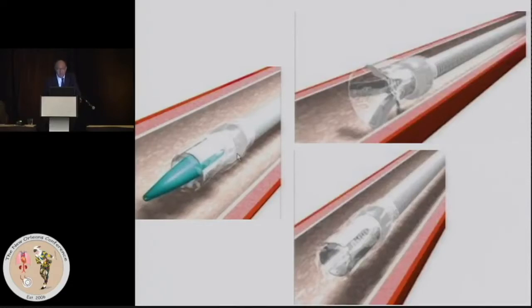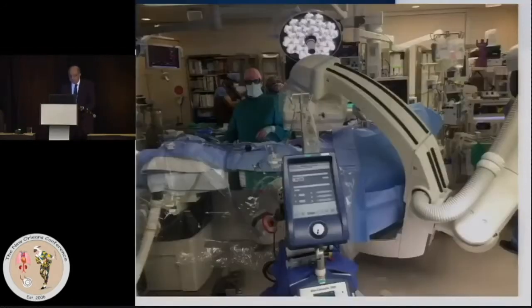And when you expand the balloon, the tip opens up into a funnel shape. Obviously, as you're advancing it over an introducer, you want the tip to be closed so that you don't engage the vessel walls as you're advancing it, and you only open it up when you're near the target that you want to aspirate. So let me show you a case.